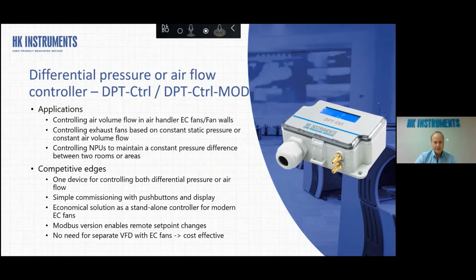And then we have this DPT control also in the Modbus version, and the Modbus version has some extras because you can make this kind of remote set point changes nowadays with the control mod. So it has inputs, for example, for a relay switch. So you can bring the relay information to the input, and you can choose between the low and the high set points. And you can get the Modbus to connect it to the BMS. So it means that you can change the parameters and the set points easily from the bus. So you don't have to go there as a person near this device to make adjustments. So it's a very easy to use device.